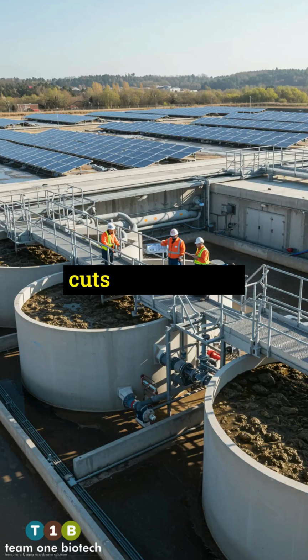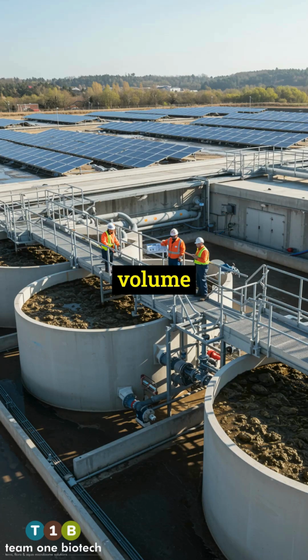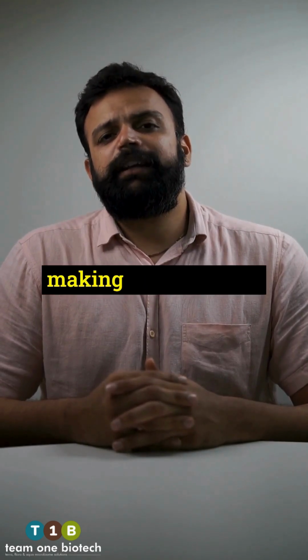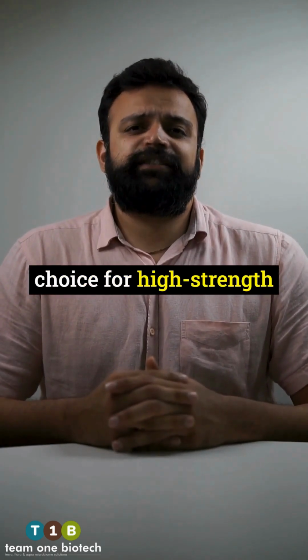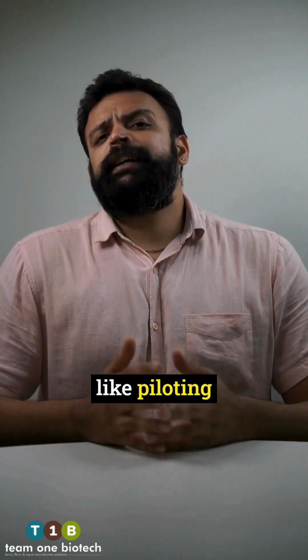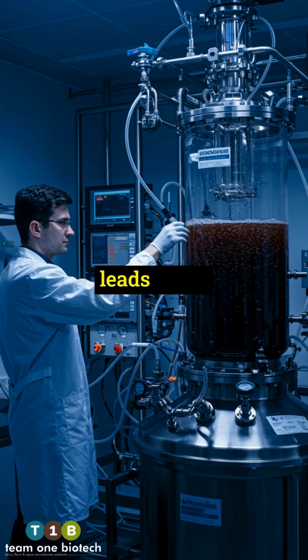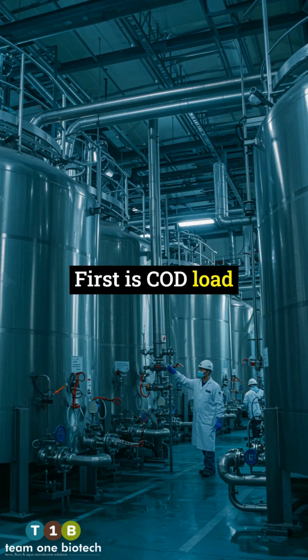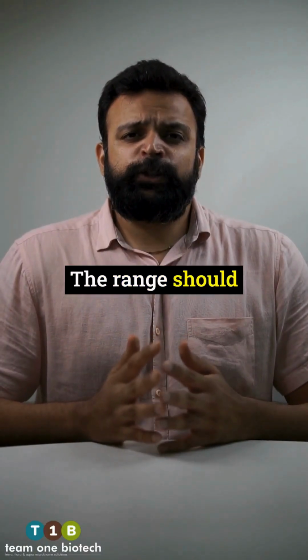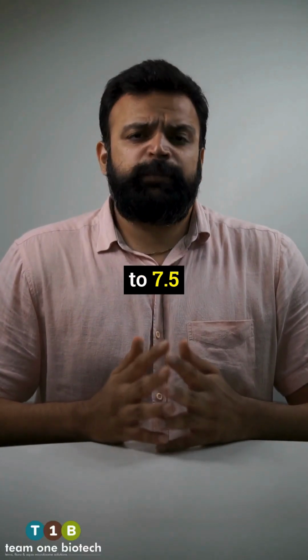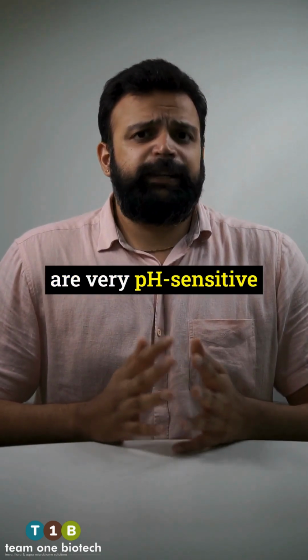This process cuts energy costs, reduces sludge volume, and recovers energy, making it a sustainable choice for high-strength COD. Controlling an anaerobic bioreactor is like piloting a submarine. Subtle changes lead to big serious consequences. Let us explore some operational parameters which are necessary. First is COD load. The ideal rate should be between 2 to 15 kilograms per meter cube per day. Second is pH. The range should be between 6.8 to 7.5 as methanogens are very pH sensitive.